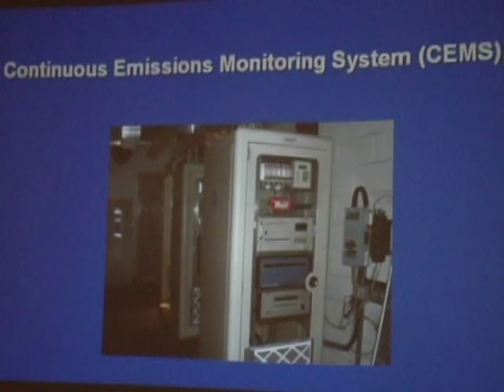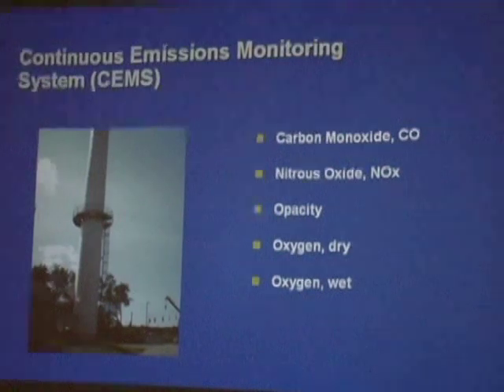The CEMs, continuous emission monitoring system, we didn't do too much with this system. We did take it off the third unit, the third RTO, because it's just doing odorous air now, so they didn't require monitoring. We only have monitoring on RTO 1 and 2. But we did have to tie the CEMs into the SCADA system. And you still have opacity monitoring and NOx, CO, and oxygen. CO, nitrous oxides, opacity, oxygen, wet and dry.